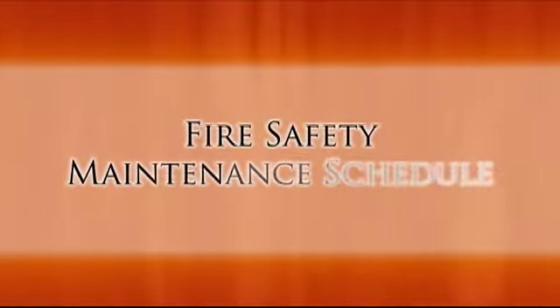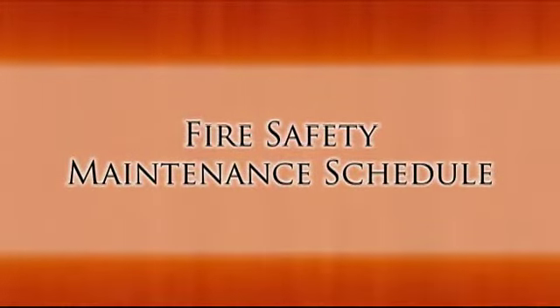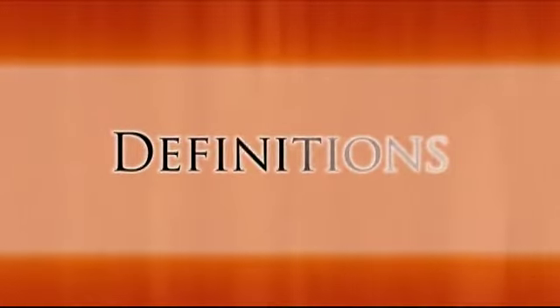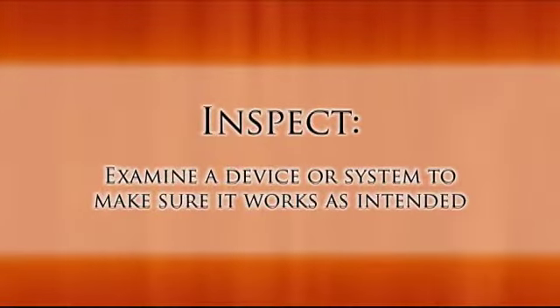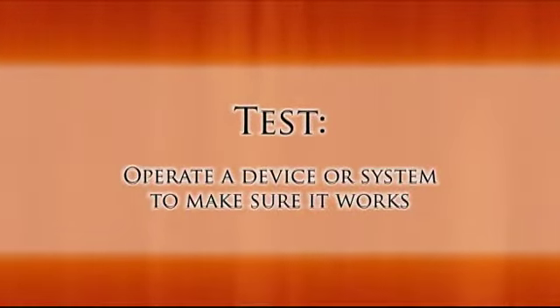In this part of the video, we're going to take a look at the various inspections and tests required by the National Fire Code of Canada that'll keep your system ready when needed. For the purpose of carrying out your maintenance procedures, the following definitions need to be remembered. Inspect means visually and physically examine a device or system to make sure it works as intended. Now, inspecting a device does not require its operation. Test means operating a device or system to make sure that it works as intended.